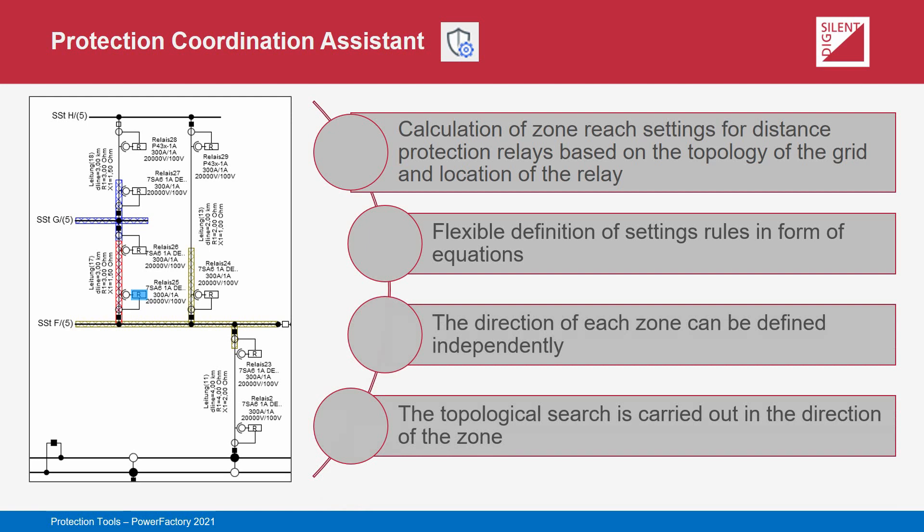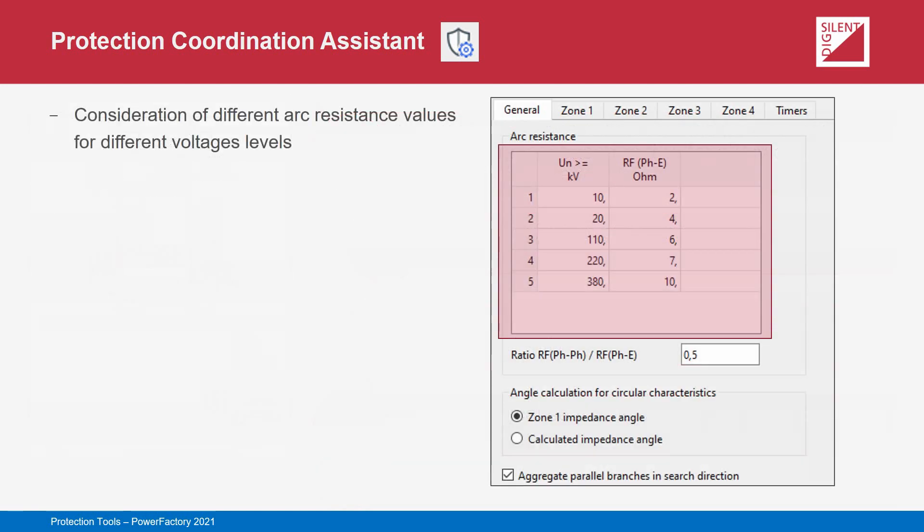For each zone, an operating direction is independently specified and this direction also determines the direction of the topological search. The search needs to be able to determine which relays are expected to coordinate with one another, and this is identified from an orientation setting associated with the CTs supplying each relay. The Protection Coordination Assistant process is carried out in two parts. During the first step, the coordination setting rules are defined, the topological search is carried out, and the settings are calculated. During the second step, the calculated settings are reported and accepted settings are transferred to the relay model.